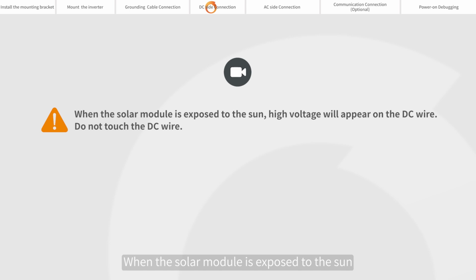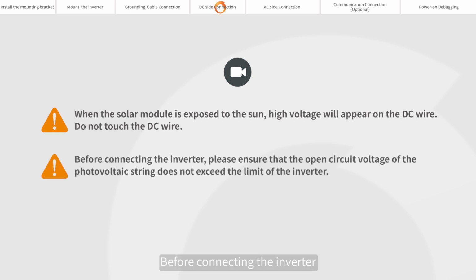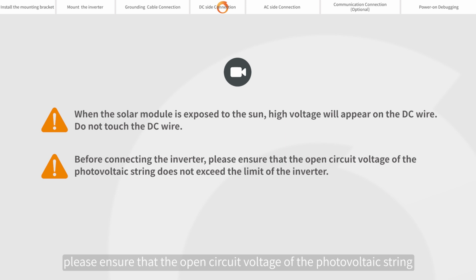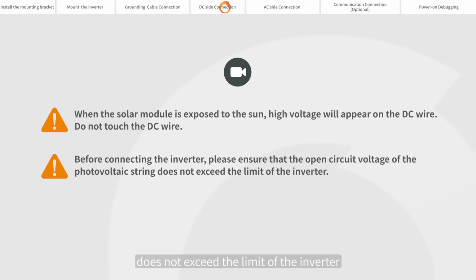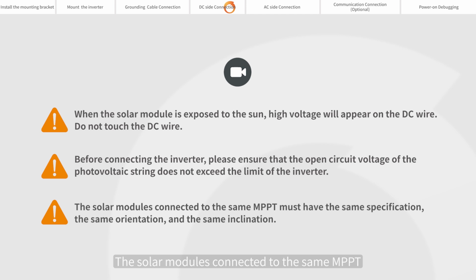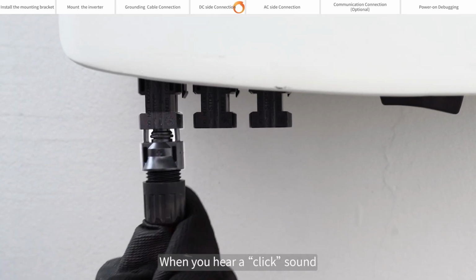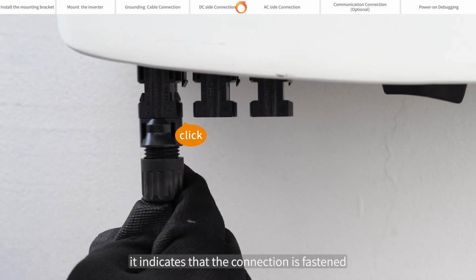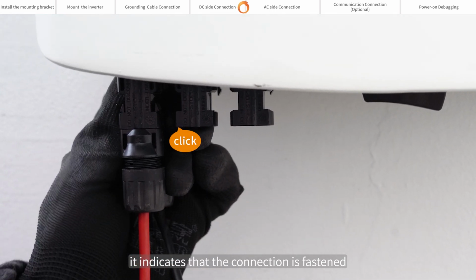When the solar module is exposed to the sun, high voltage will appear on the DC wire. Do not touch the DC wire. Before connecting the inverter, please ensure that the open circuit voltage of the photovoltaic string does not exceed the limit of the inverter. The solar modules connected to the same MPPT must have the same specification, the same orientation, and the same inclination. When you hear a click sound, it indicates that the connection is fastened.